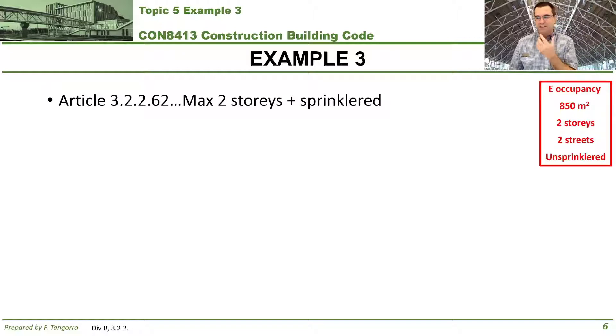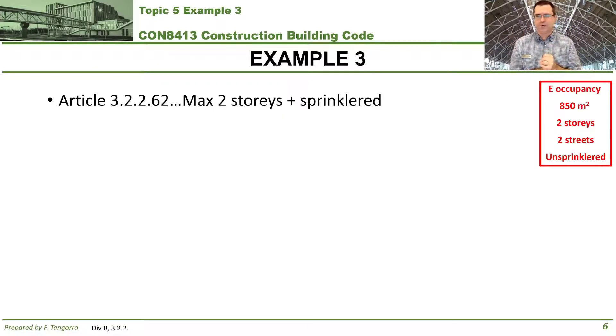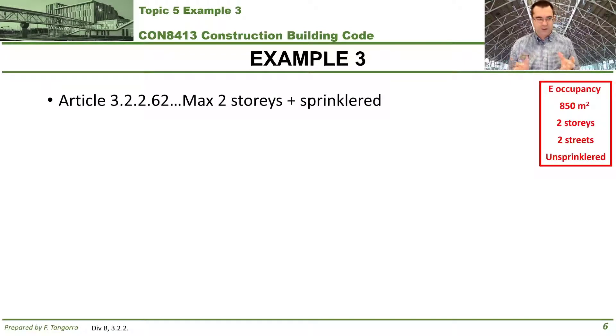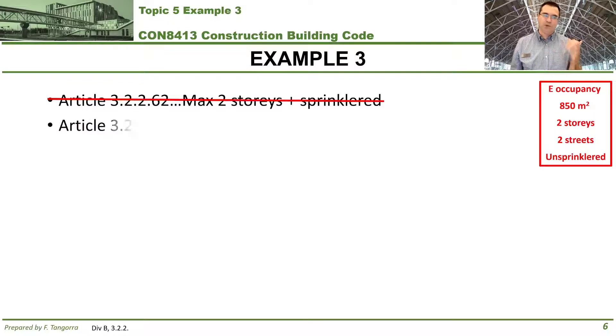We're going to start with the last of these five articles: Article 3.2.2.62. This article, as you know by reading it including its title, applies to a maximum of two-story buildings that are sprinklered. Does that apply to us? It could — it says max two stories and our building has two stories. But our building is unsprinklered and this article is only for sprinklered buildings. No good. We get rid of this one and keep on moving backwards.